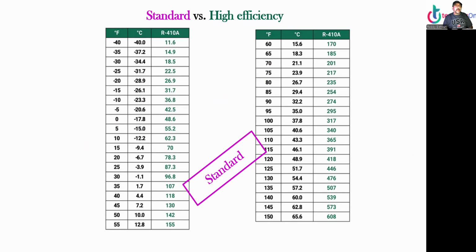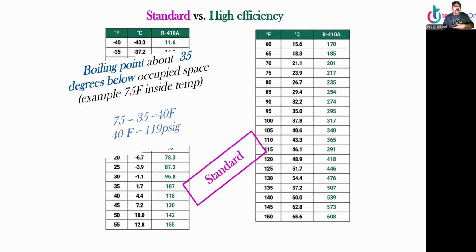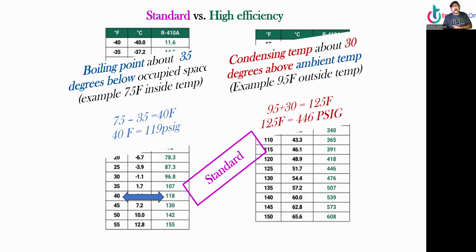Okay, now standard versus high efficiency. That's why we replace units, because they become more efficient as we go on. Boiling point, let's say now, standard, old school. The boiling point should be about 30 to 35 degrees colder. So a typical air conditioner should be running about a 40-degree boiling point. That's 119 psig.